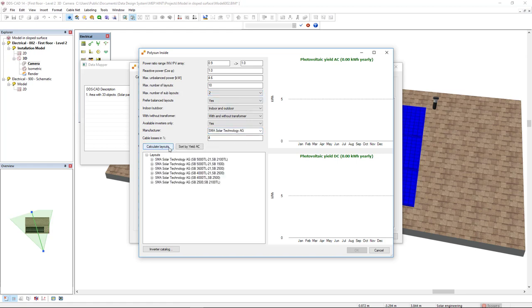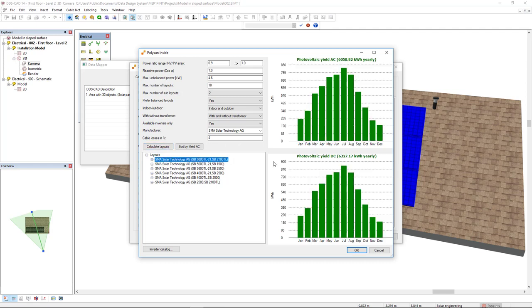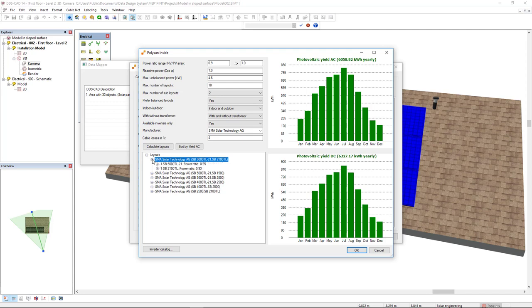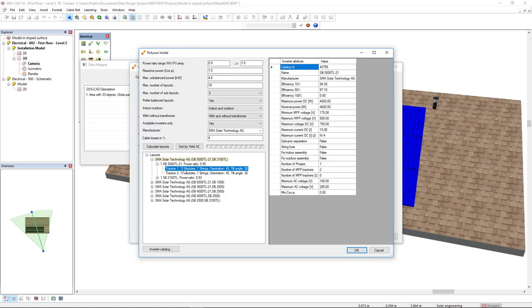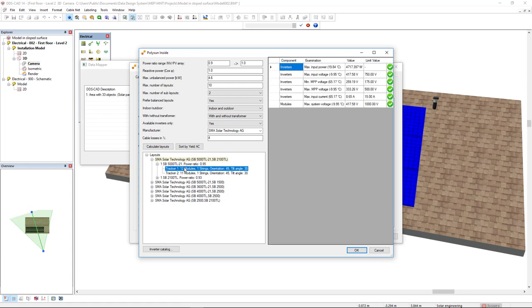Here we see a list of layouts that we have found. I will click on its first entry. And DDS-CAD has calculated the AC/DC values. By clicking on the plus sign, here you see the technical specifications of the SMA inverter. Also, we see the exact amount of modules per string and tracker. If we click on a tracker, we can see that all calculated values are not exceeding its limits, making this a suitable PV inverter combination.